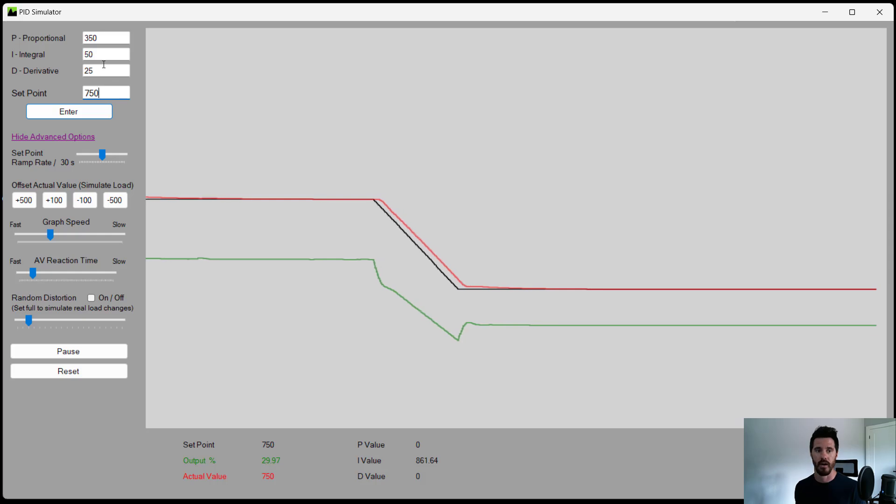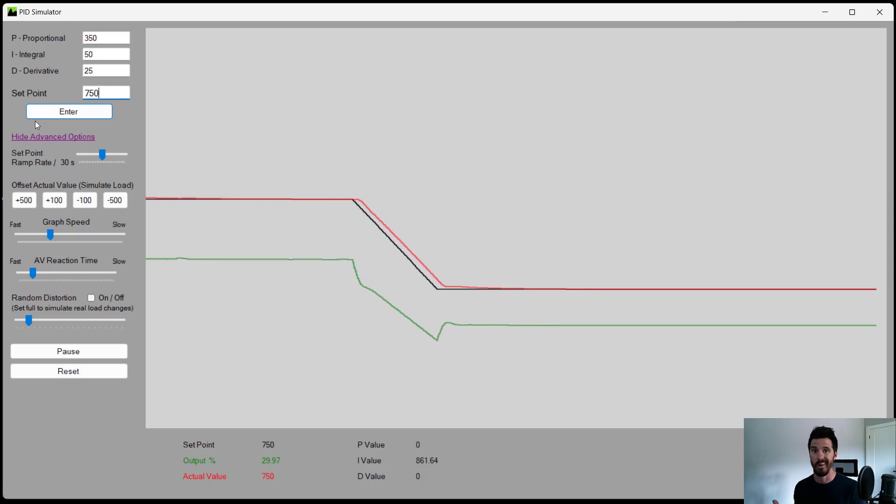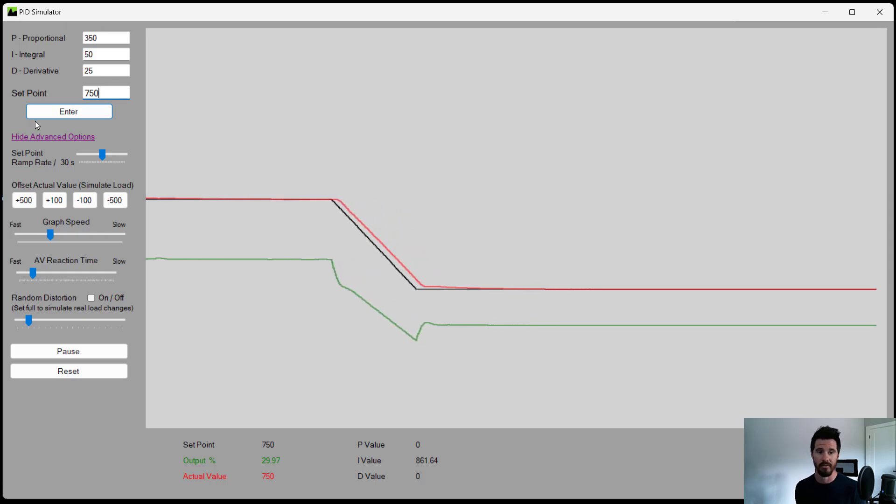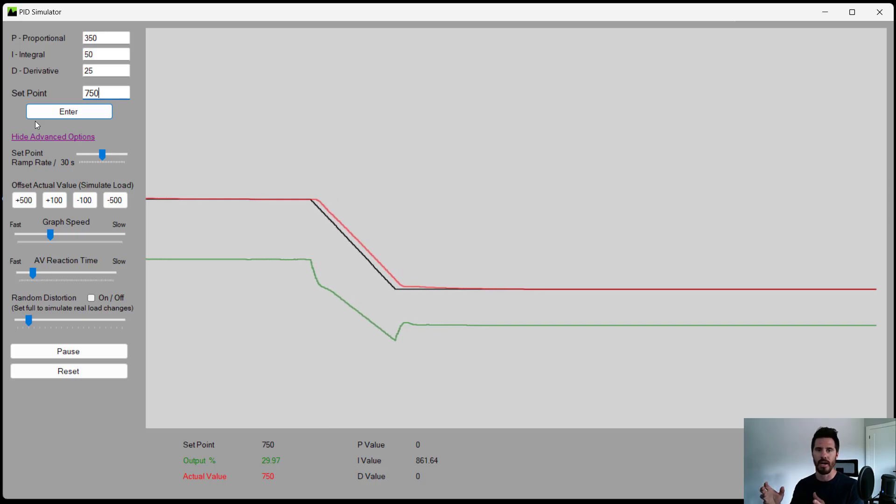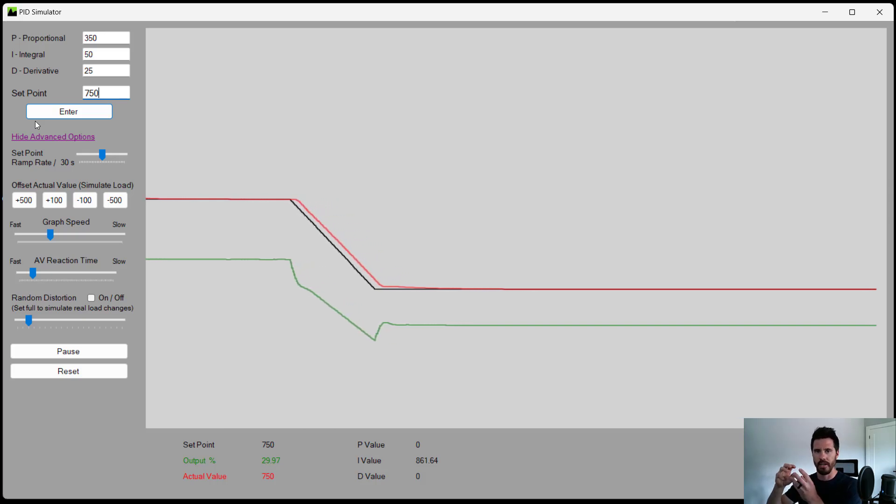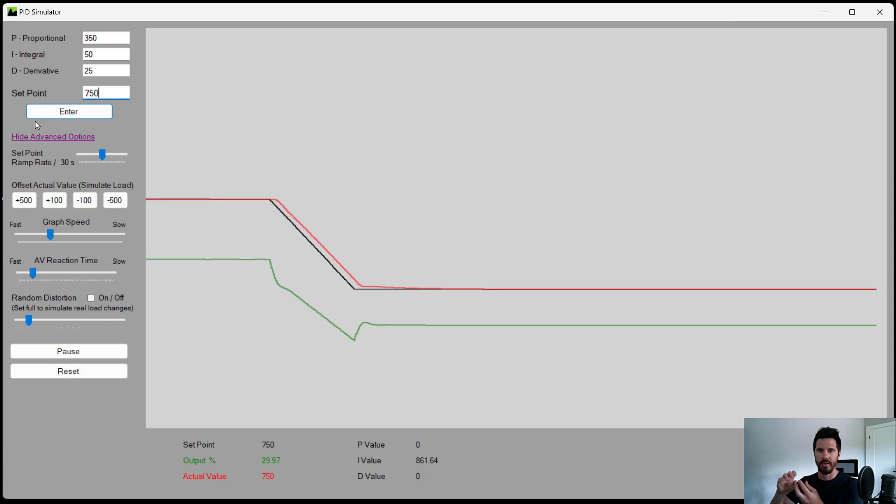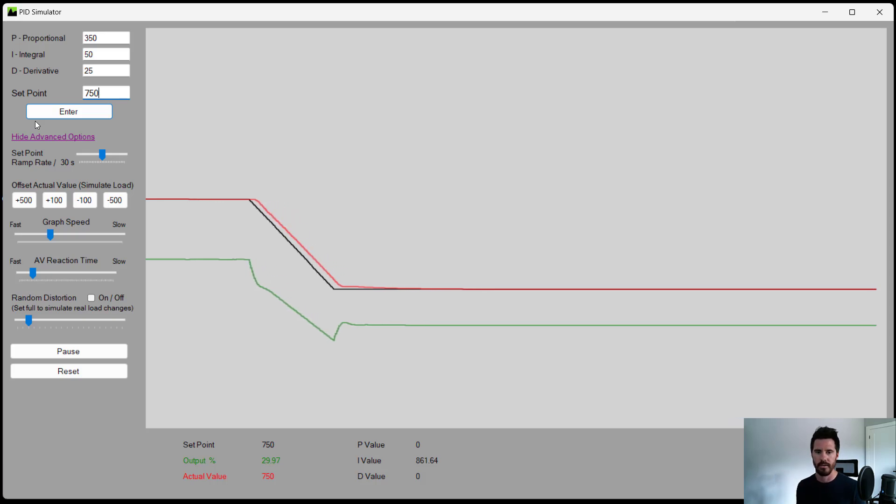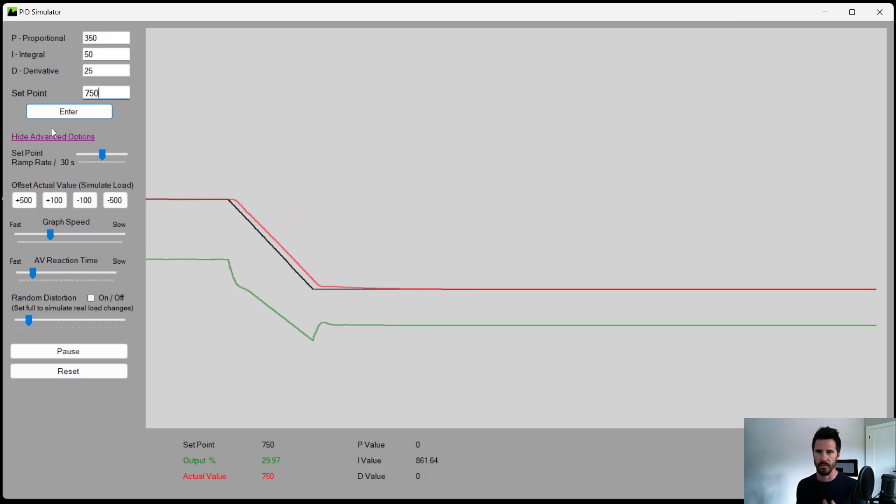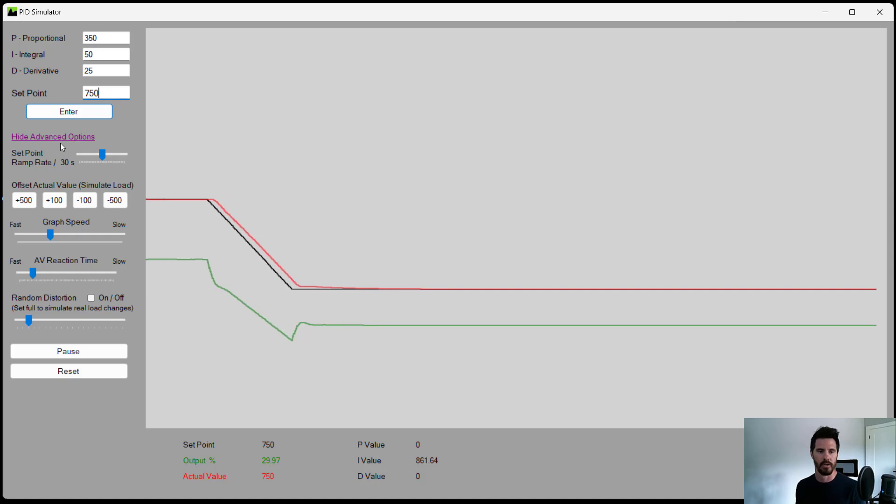These 350, 50, 25 on this controller might look like 110, 5 on another controller because every manufacturer has a little bit of a different calculation or multiplication or gain factor on their PID values. But once you learn how to tune, then you'll be able to figure it out for each manufacturer.